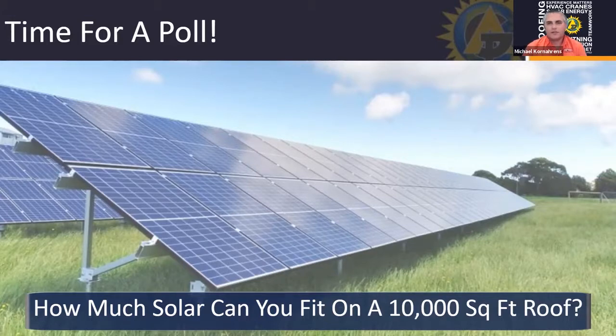There have been a couple other questions here that I'll address. One of the questions was, hurricane season's coming, there's a high rise building, what wind speeds can the solar panels sustain? The highest one that I believe we've been involved in is a 164, 165 engineered system. The glass panels are double-sided glass. They're very structurally sound. So what we do is we enhance the rails and the attachment methods of the system. There are different ways you can attach them to the roof: fully mechanically attached, a ballast hybrid system, or a full-on structural steel system. So we have all different kinds of systems that will meet those wind loads.